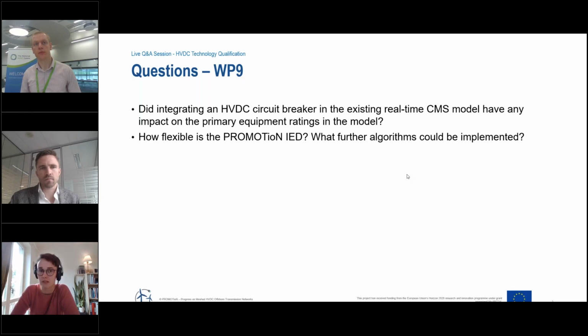And then if you still want to test with a real-time system, you would have to go from analog input to something optical. That would require a larger hardware change, but it's a plug-and-play design, so I believe it's possible. And for the actual implementation of algorithms, it's a dual-core ARM processor, so it's quite powerful. I'm confident that even a bit more computationally heavy algorithms could be implemented. Okay, good. And could you maybe also comment on whether the types of signals and the right sort of bandwidth that you need for this IED are present or available in converter stations that have been built today?